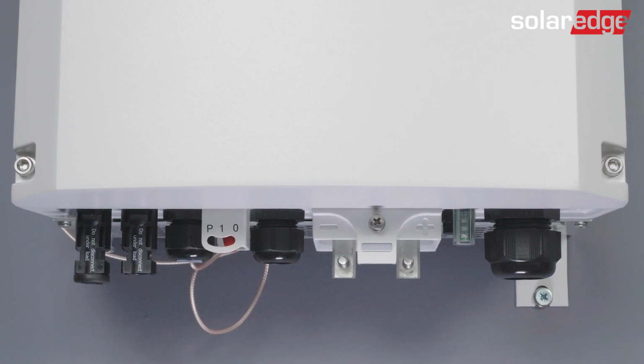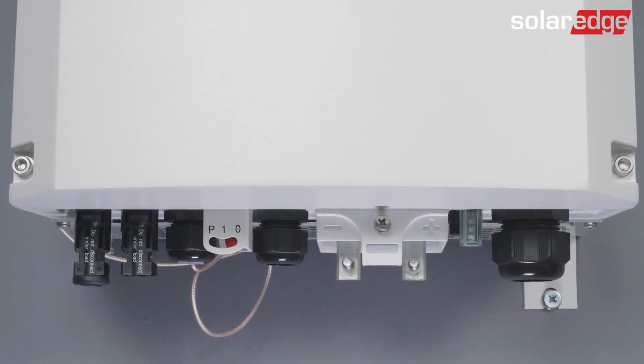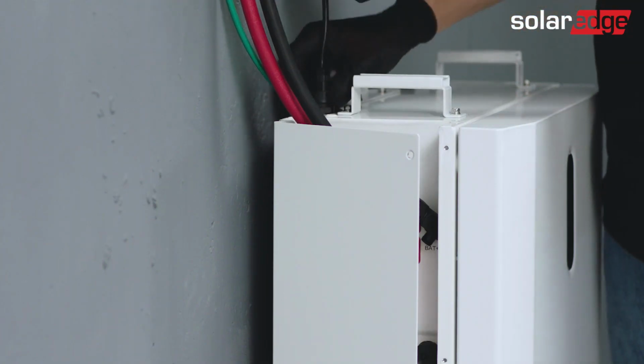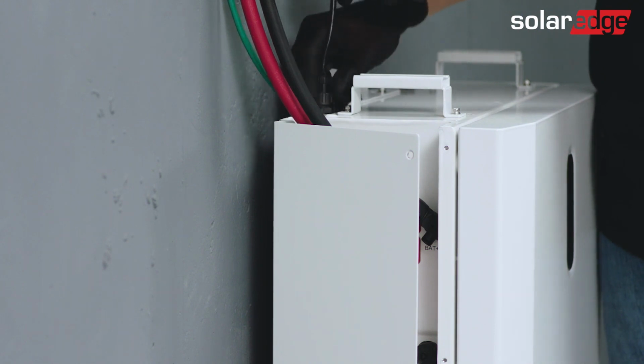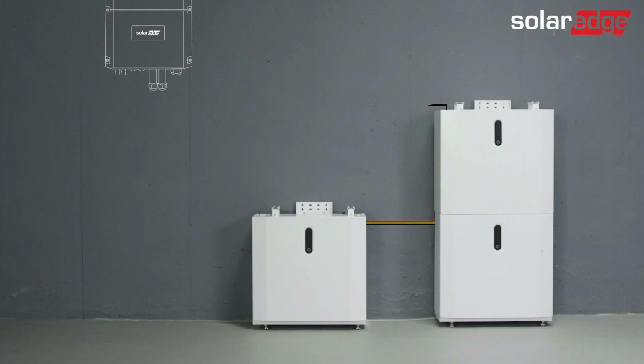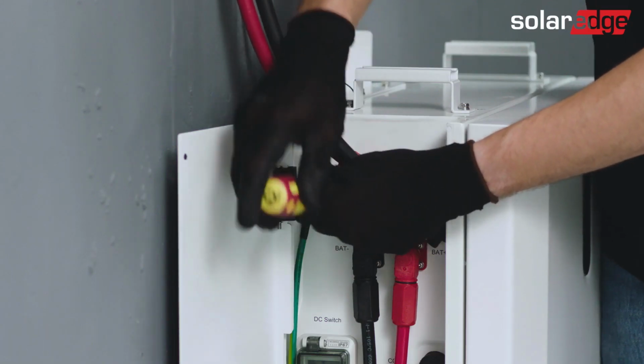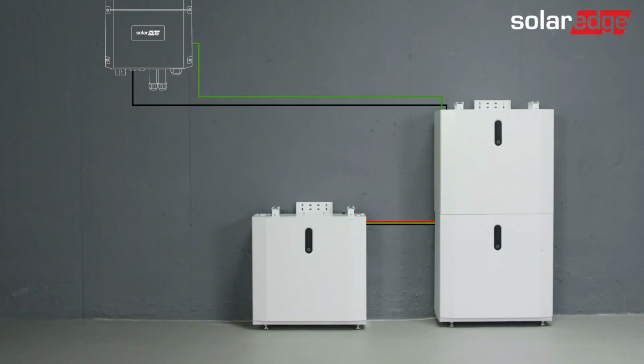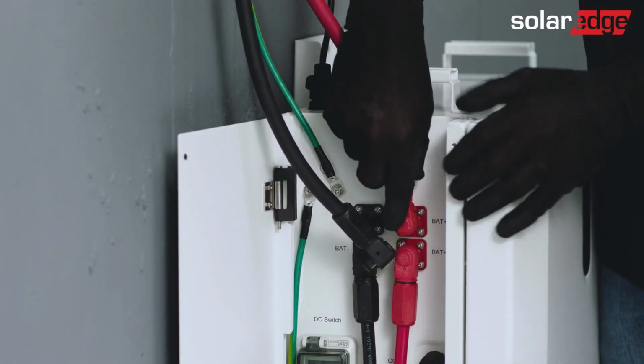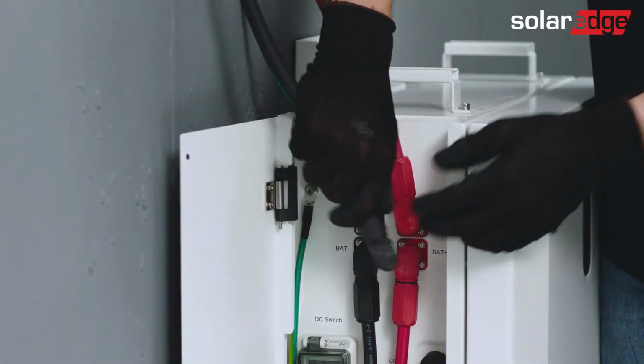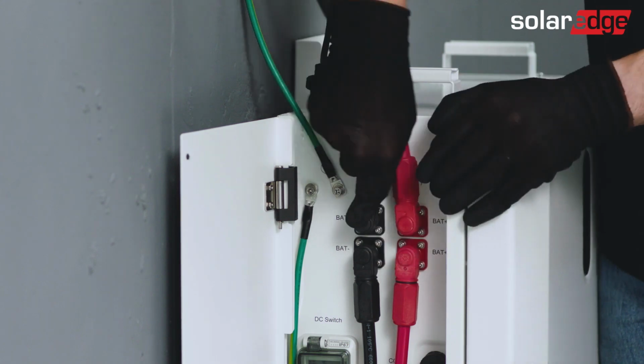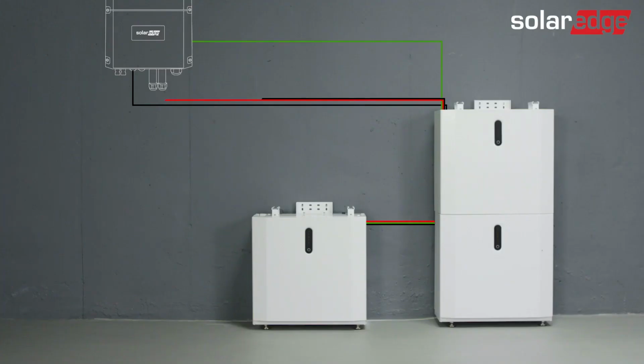Before connecting to the inverter, make sure it is off. Connect the communication cable to the top battery's connector marked with INV. Then, connect the communication cable to the inverter. Thereafter, make sure to connect the grounding cable to the utility ground. Lastly, connect the red and black DC cables from the top battery in the tower to the inverter. Pay attention to the polarity at the inverter side.